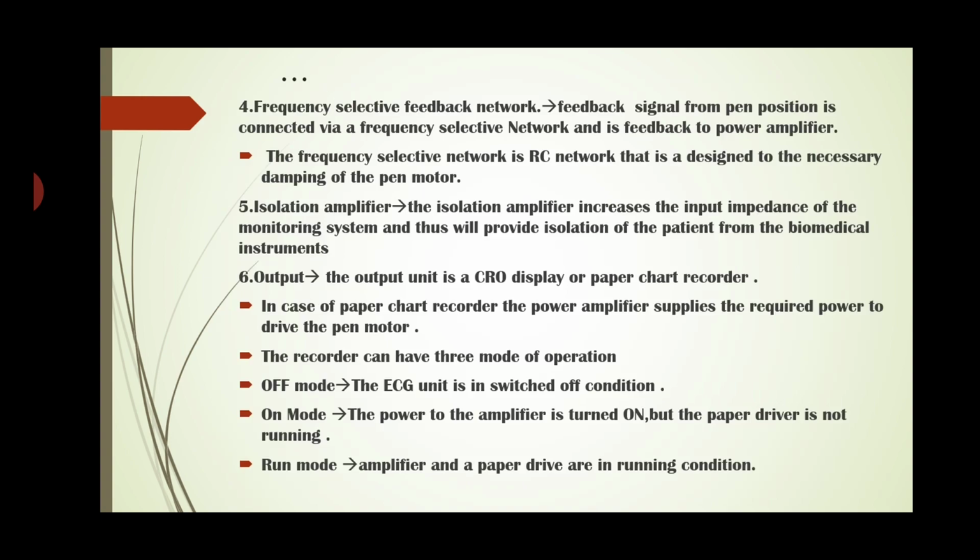In the paper chart recorder, to record the ECG signals, they are using wax coated paper and a heat sensitive pen is used. So whenever the heat sensitive tip moves on the wax coated paper, then we are getting the recording of the ECG signals.